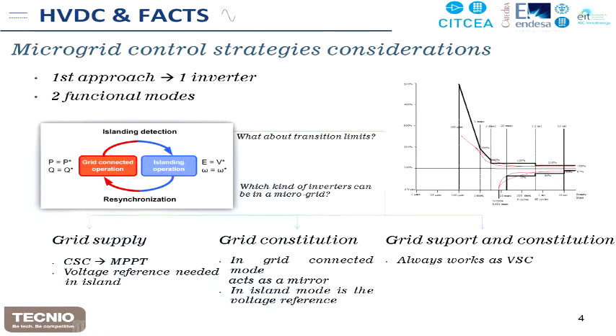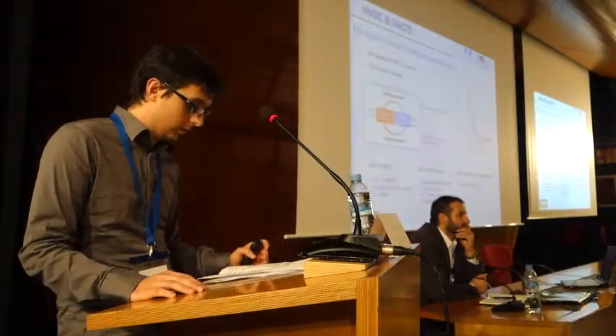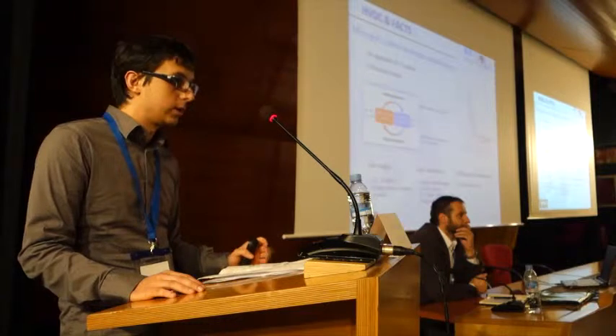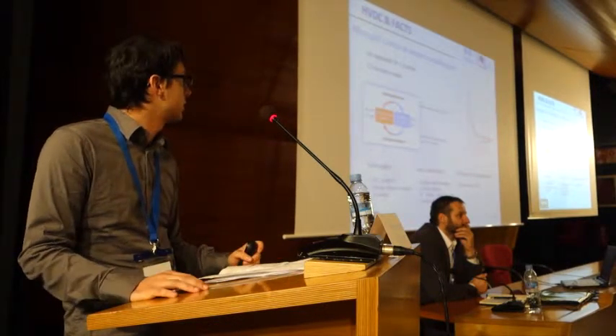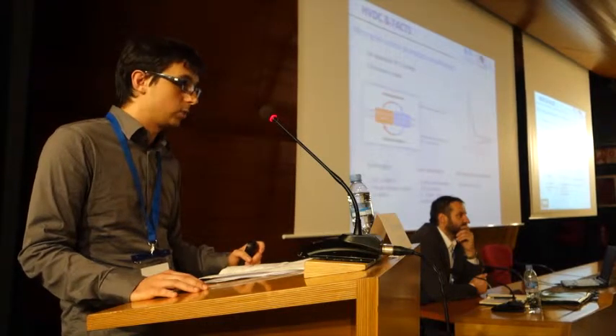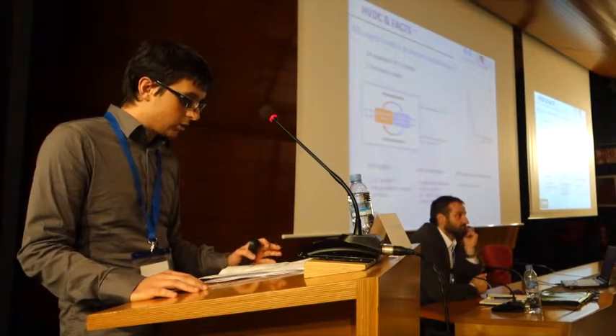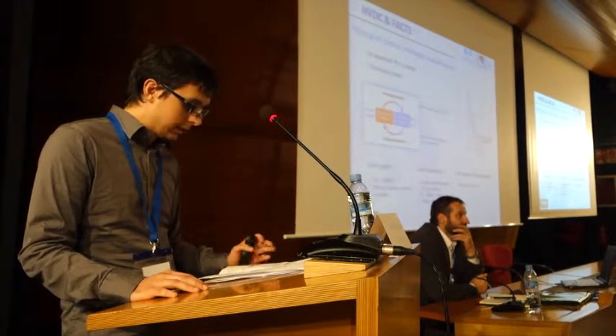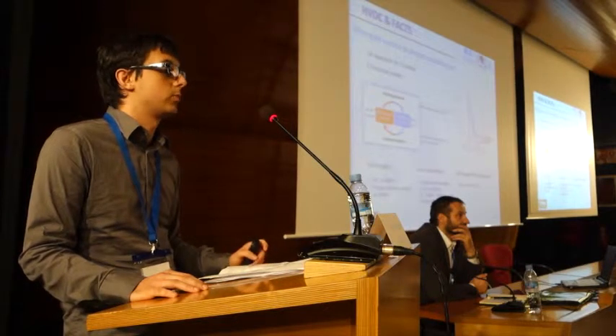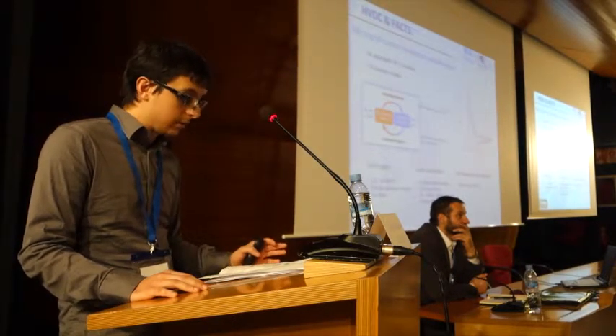Okay. So, giving only some control strategy considerations, it's important to say again that if we are thinking about the integration of these energy storage systems, thanks to power converters, we can operate the system considering two operation modes on the AC side: the grid-connected operation mode, where we need to follow active and reactive power references, and the islanding operation mode, where we need to guarantee the stability and robustness of the voltage and frequency that we are generating for our loads. But that is not all. It's really important also to consider how we can do the transitions between modes. This implies, what about transition limits?